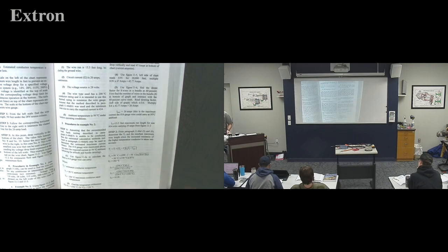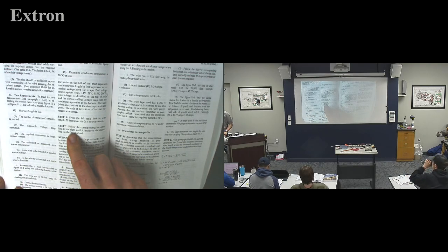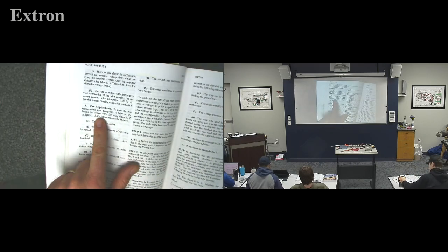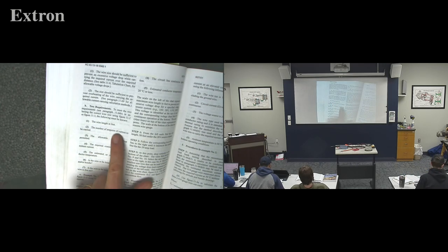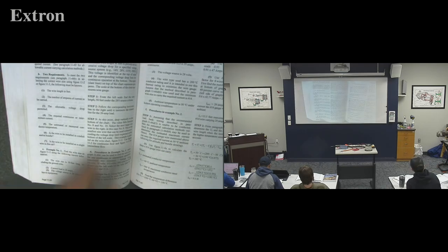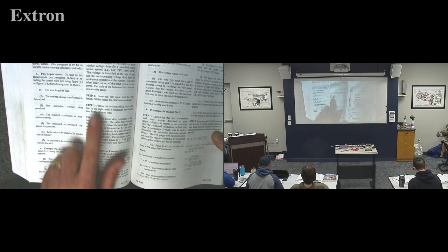It gives you some info. It talks about altitude, it talks about copper versus aluminum. And it starts out basically over here where it says 2 requirements: the wire length, the amperage, the allowable voltage drop. So it asks you all these questions, and then you check step 1. You go through a chart on step 1, then step 2, then step 3.